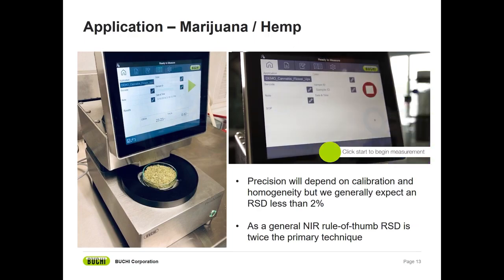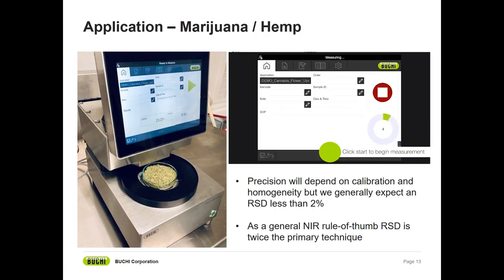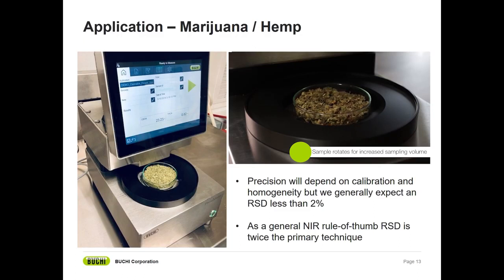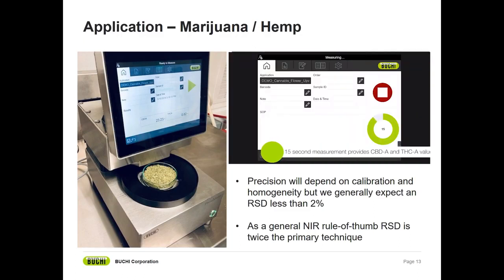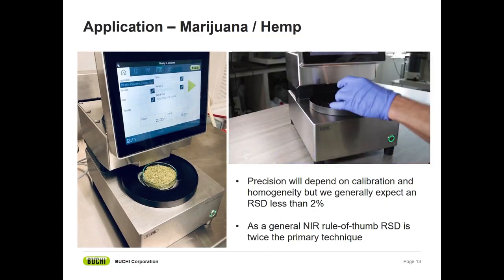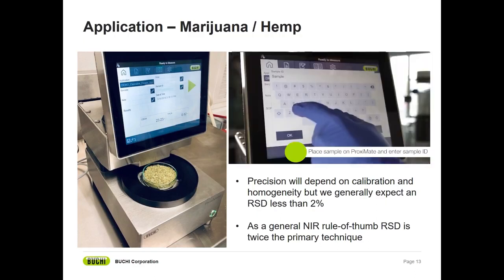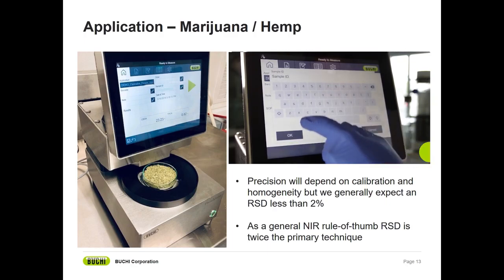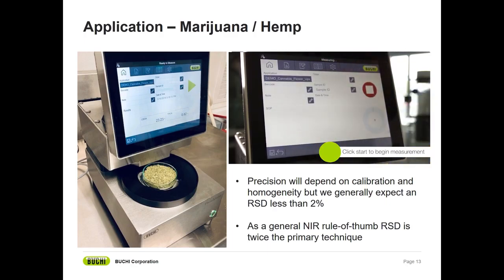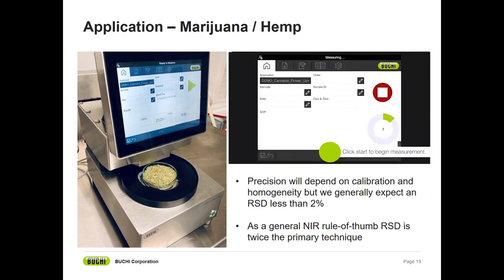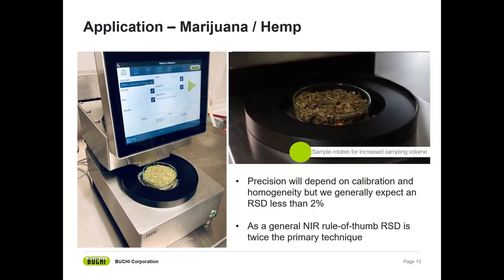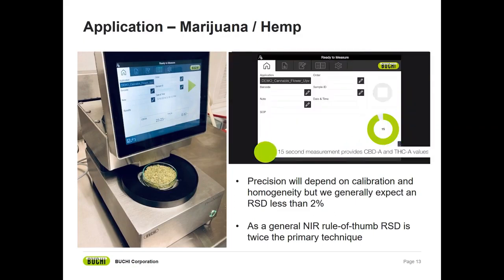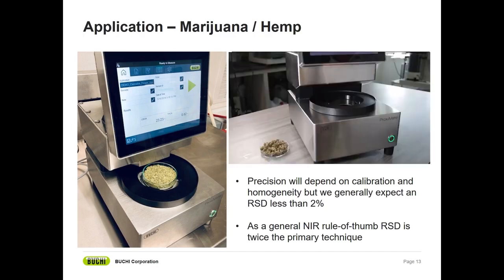This is great and will serve as your primary method, but you'll still be limited to how many samples you can run per day and where you can run those samples, meaning all liquid chromatography has to be in a clean lab environment. You wouldn't even think about running these samples out by the truck where your raw material is being unloaded. NIR changes the game on that. Adding to the workload of LC is the fact that for a flower material, you'll first have to prep the sample to get the extracted material into an injectable form. With the NIR, the sample prep is completely reduced to typically just a simple grind of the flower.